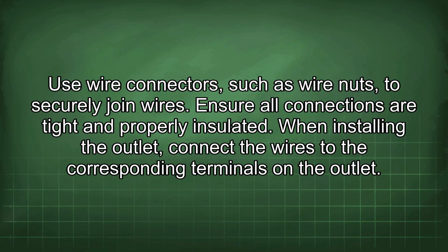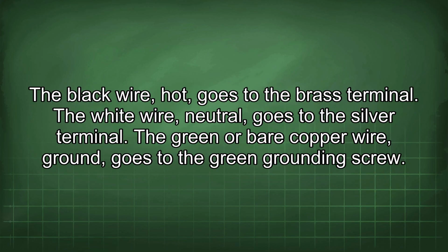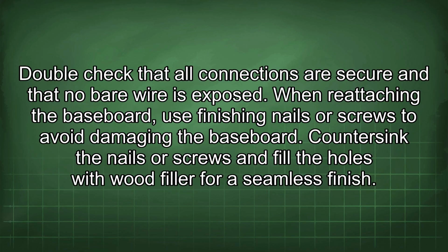When installing the outlet, connect the wires to the corresponding terminals on the outlet. The black wire, hot, goes to the brass terminal. The white wire, neutral, goes to the silver terminal. The green or bare copper wire, ground, goes to the green grounding screw. Double check that all connections are secure and that no bare wire is exposed.